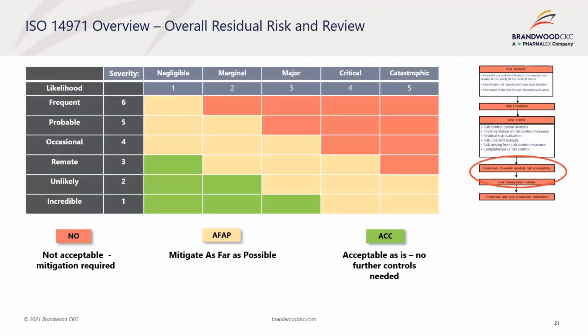jurisdictions. Residual risks are evaluated by the same method and with the same criteria for risk acceptability as the initial risks. The residual risk is either acceptable or unacceptable. When unacceptable, further risk control options should be investigated. If further risk control is not possible, a benefit risk analysis may be performed. Residual risk evaluation can be repeated through the life cycle of the medical device, when the production and post-production information indicate that either the risk or its acceptability could have changed.